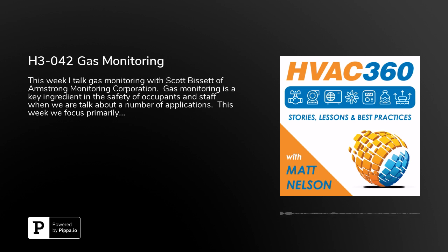And two, I could point this out: when we talk about alarms, it's going to be mostly on the refrigerant side. Are you alarming the vehicle exhaust, or is it just a fan kicking on? In many cases, yeah. We typically encourage people to look at what they want to have happen when, and generally speaking, our alarms are done in conjunction with the two established exposure limits. One is an 8-hour average exposure, and the other is a 15-minute short-term exposure limit.